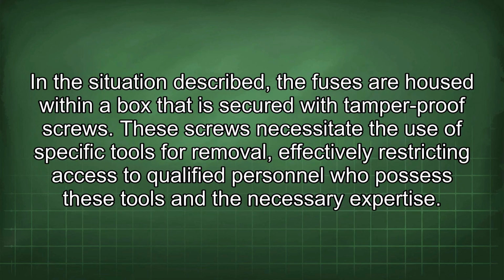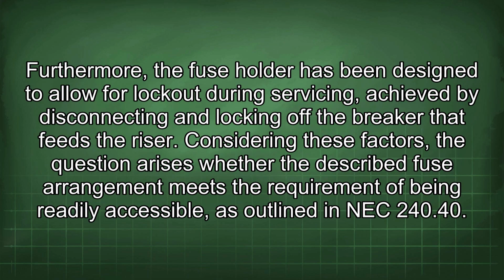In the situation described, the fuses are housed within a box that is secured with tamper-proof screws. These screws necessitate the use of specific tools for removal, effectively restricting access to qualified personnel who possess these tools and the necessary expertise. Furthermore, the fuse holder has been designed to allow for lockout during servicing, achieved by disconnecting and locking off the breaker that feeds the riser.